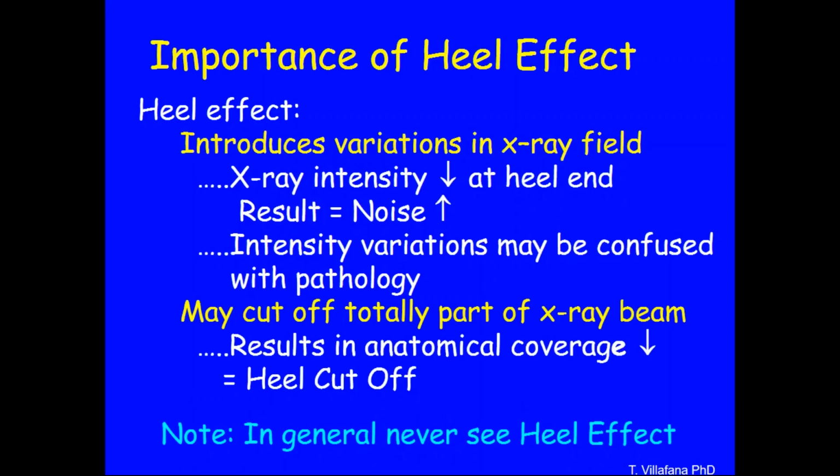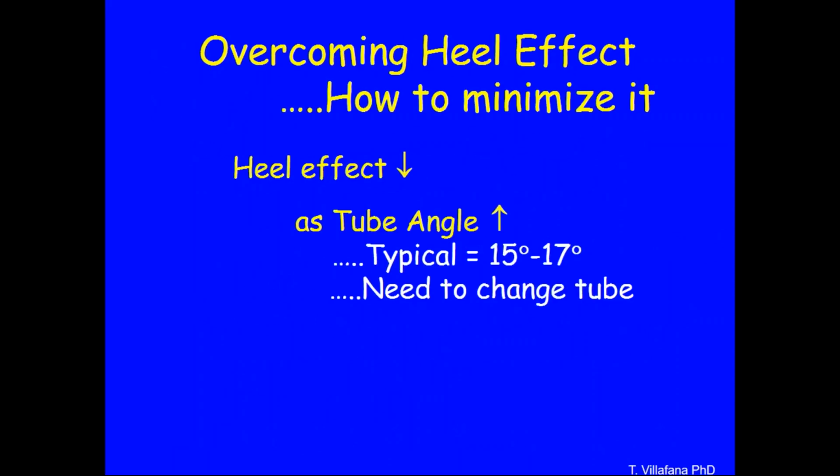When the engineer first installs an X-ray tube and takes his first test shot, if he sees heel effect, he knows something's wrong. And he'll make sure that you never get to see it. He'll have to change tubes or do something about that heel effect to prevent it.